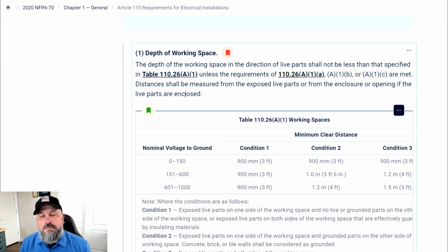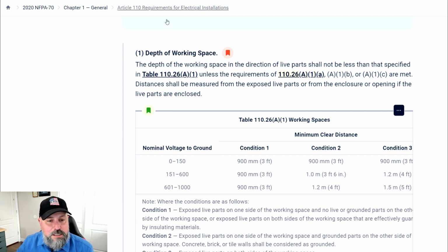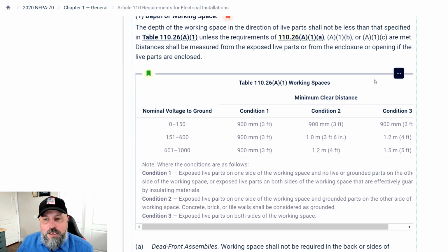If the device is enclosed, if it's in a cabinet, if it has a cover on it, then you are going to be measuring it from the outside of the cabinet. The measurement is not from live parts unless those are exposed live parts at all times. If it has a door, if it has a removable cover, it has to be measured from that cover to wherever you're measuring from. So I wanted to be clear on that. And so right here, we're going to expand this table and go into this.